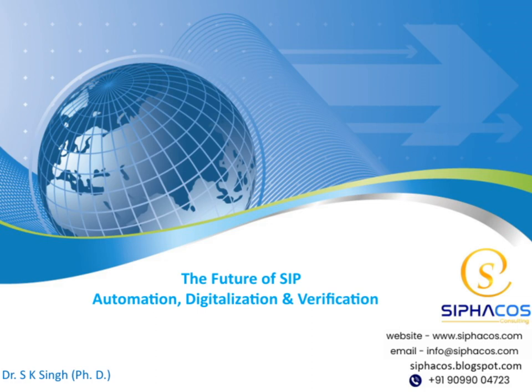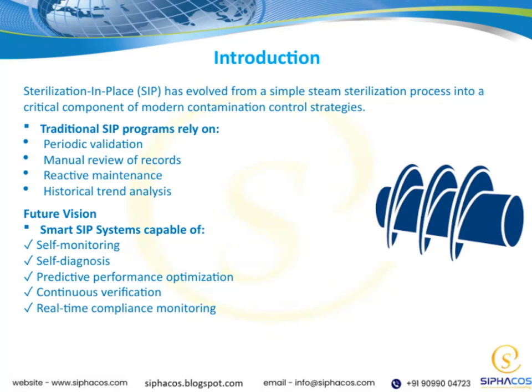Let's start by looking at sterilization in place, or SIP, and how it's grown beyond just steam sterilization. Traditionally, SIP programs depend on periodic validation, manual record reviews, reactive maintenance, and analyzing past trends. But that's changing. The future points to smart SIP systems that can monitor themselves, diagnose issues, optimize performance predictively, verify continuously, and keep compliance in real time. It's a shift from reactive to proactive, making contamination control smarter and more reliable.